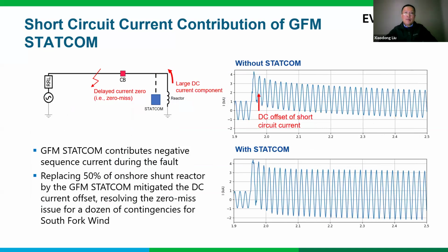All right, so one main driver, as we mentioned, of selecting the STATCOM for the South Fork Wind project was that a significant delayed current zero issue was discovered in the project, and the grid forming STATCOM helped to resolve the issue. As I mentioned previously, the 138 kV export cable is 60 miles long, which has a very large charging. So the project was initially designed with the largest reactor to compensate the larger cable charging.